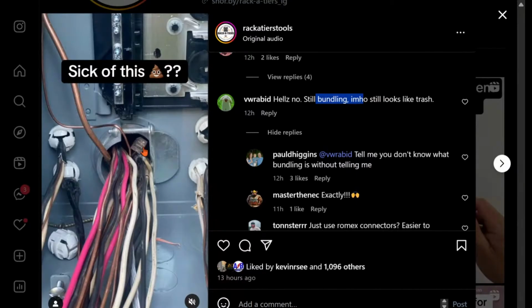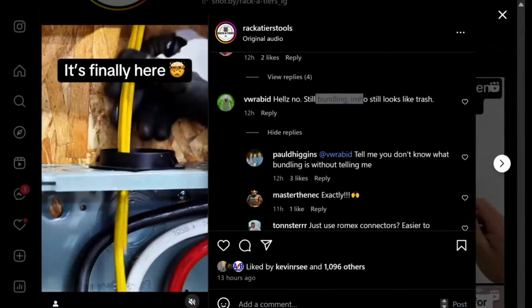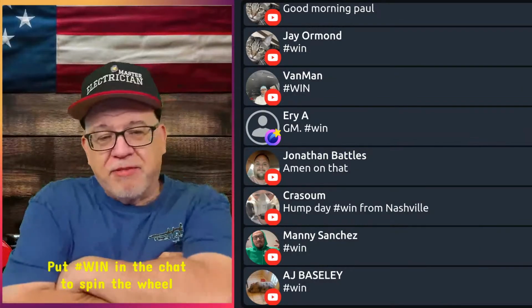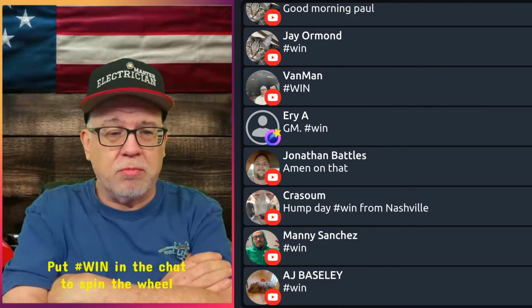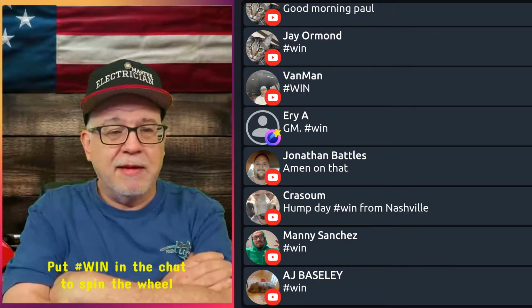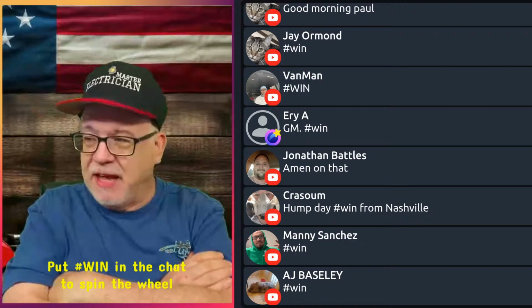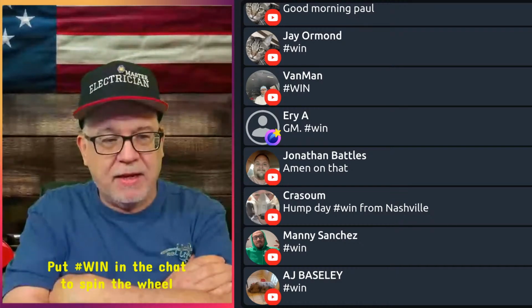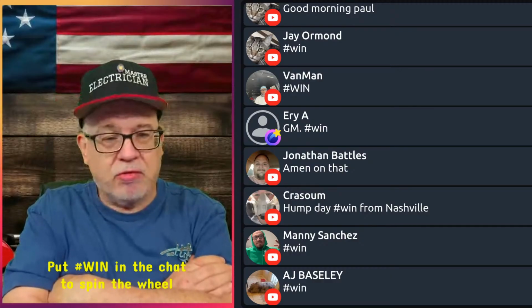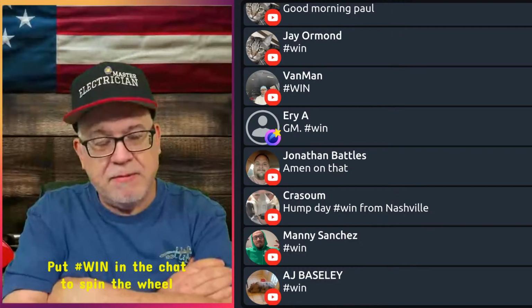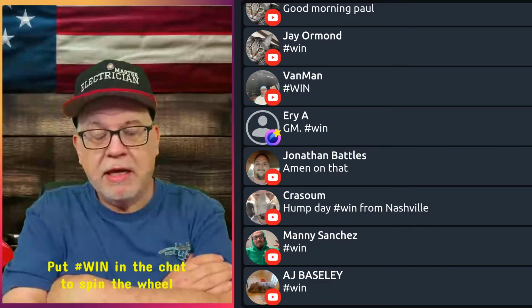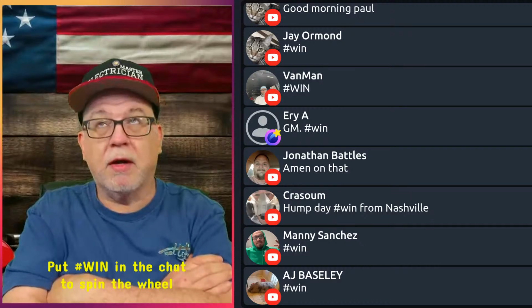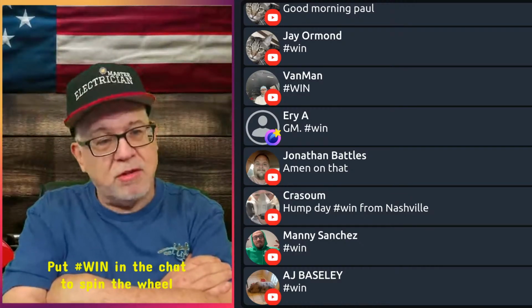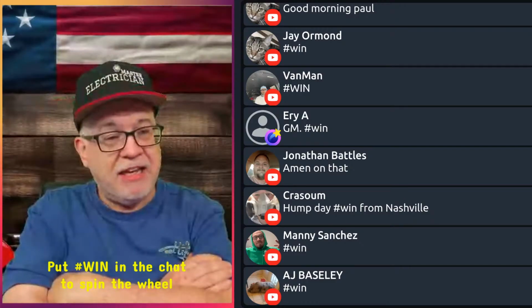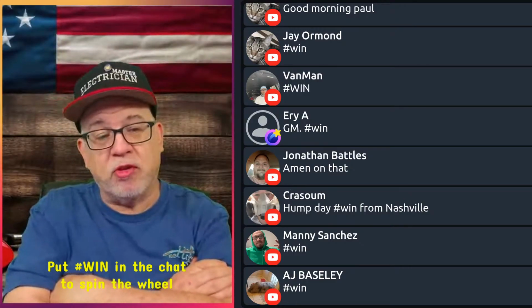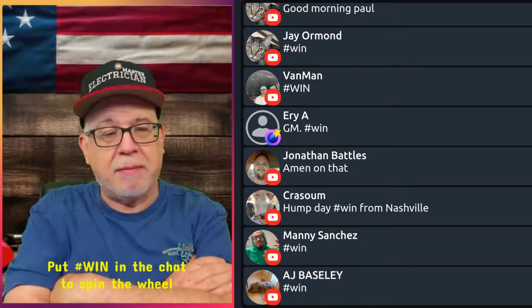It's right. So clearly, somebody doesn't have an understanding of what bundling is and what the definition of bundling is. And obviously, they've never cracked the code book open and looked at 334.80. They've never looked at 310.15(C). They have no idea what bundling is. Now, if I'm bundling cables for over 24 inches without maintaining spacing, then I got a bundling issue. If I'm bringing NM cables through a top plate, and it's going to be filled with insulation, foam, whatever it may be, then I've got issues. It's not bundling. I got issues based on the rules in 334.80 that I have to meet. It's going to reduce the ampacity of those conductors.